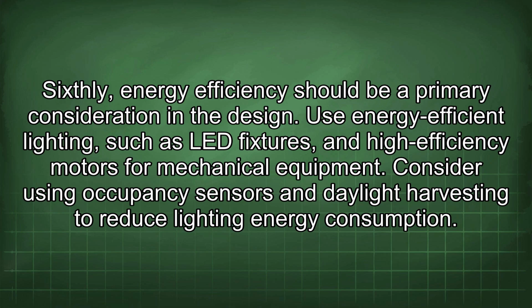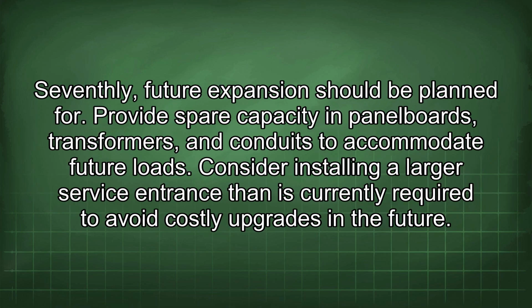Consider using occupancy sensors and daylight harvesting to reduce lighting energy consumption. Seventhly, future expansion should be planned for. Provide spare capacity in panel boards, transformers, and conduits to accommodate future loads. Consider installing a larger service entrance than is currently required to avoid costly upgrades in the future.